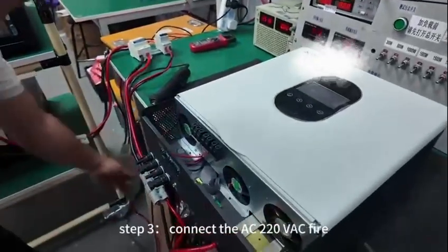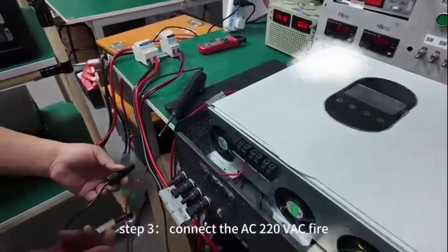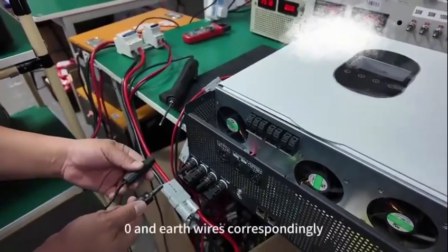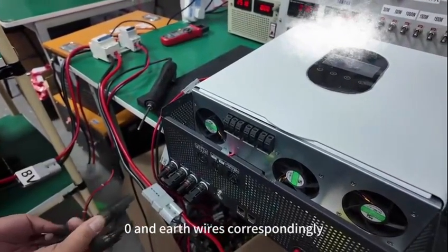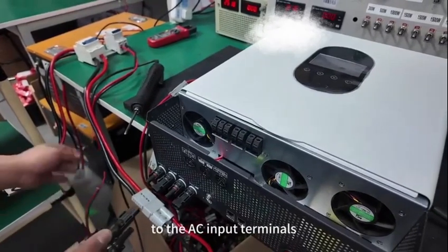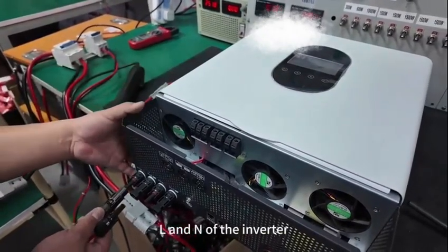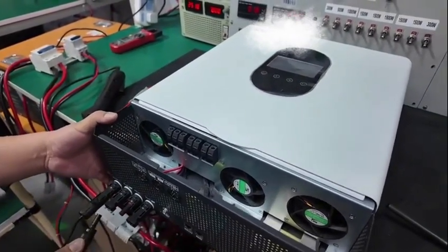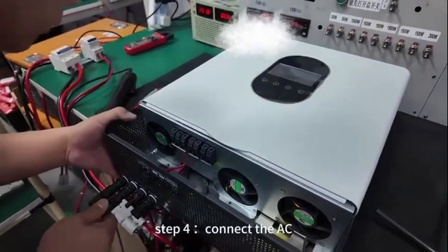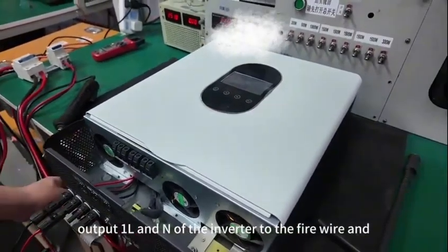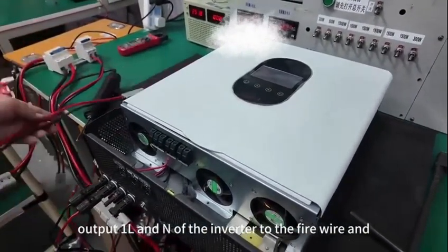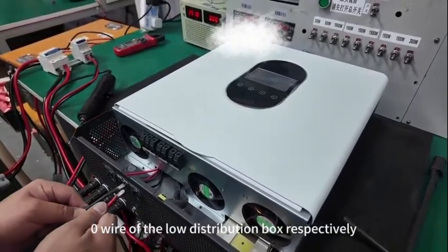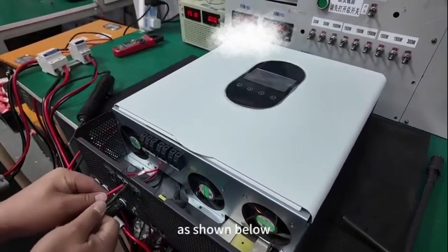Step 3. Connect the AC 220V AC fire, 0 and earth wires correspondingly to the AC input terminals L and N of the inverter and the grounding marking place. Step 4. Connect the AC output 1, L, and N of the inverter to the fire wire and 0 wire of the load distribution box respectively, as shown below.